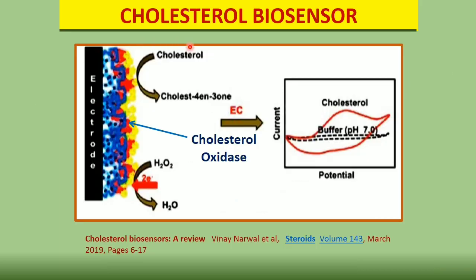Similar to the glucose biosensor, a cholesterol biosensor was developed using cholesterol oxidase enzyme. This enzyme oxidizes cholesterol to cholestenone, generating hydrogen peroxide. This hydrogen peroxide undergoes redox reaction, giving an increase in current as seen in the cyclic voltammogram — a plot of current versus potential. With increasing concentration of cholesterol, more hydrogen peroxide is generated and the peak current also increases.